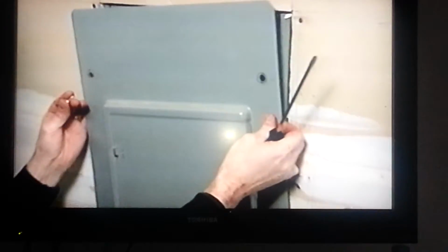When you are ready to proceed, de-energize the service panel at the main breaker. And remember, power will be out for several hours during installation. Remove the service panel cover and test the circuits to make sure they are dead. Be careful, the lead-in wires above the main remain hot.